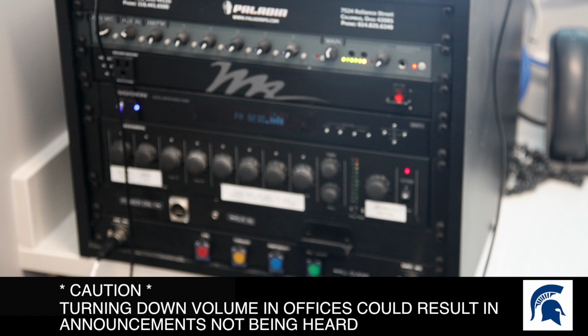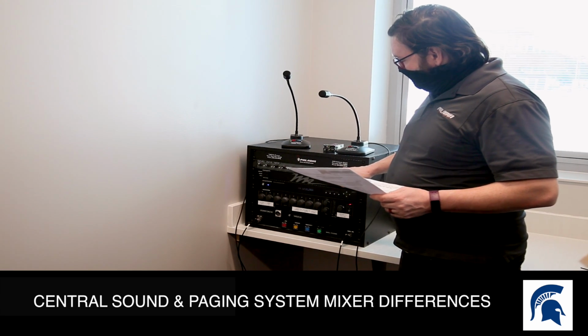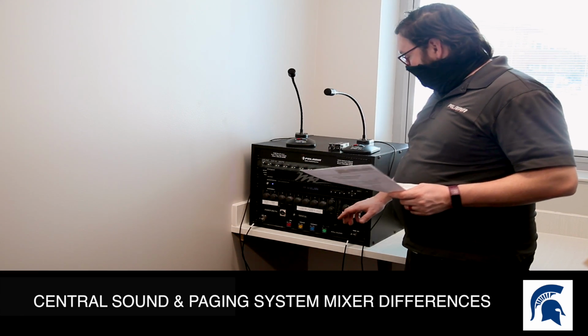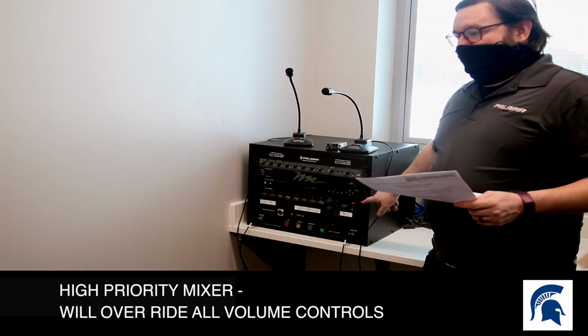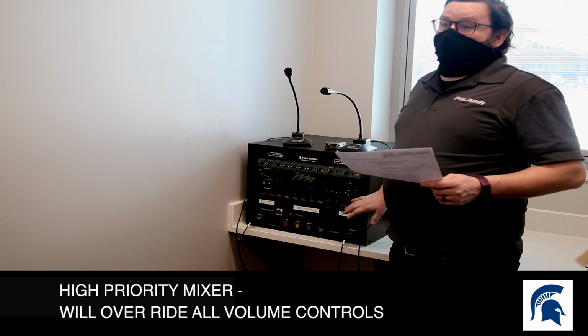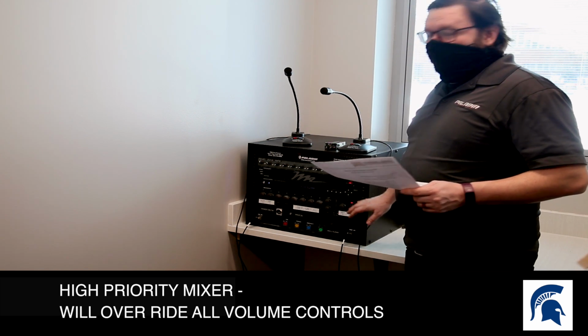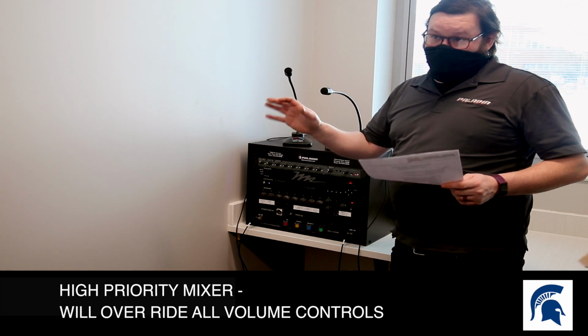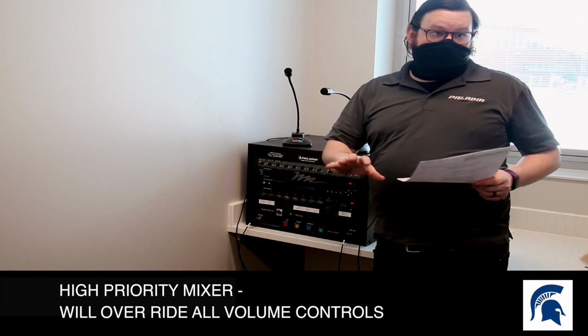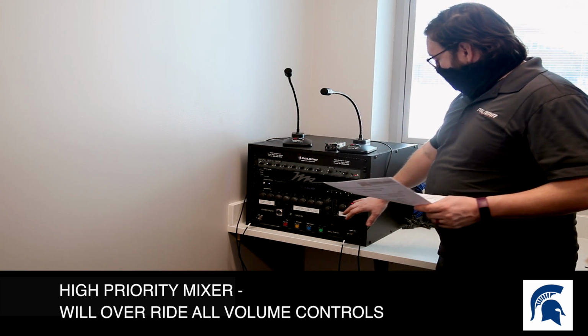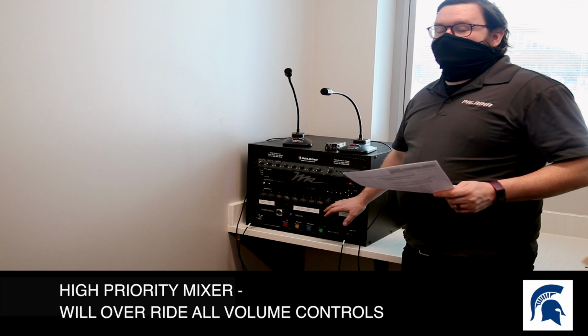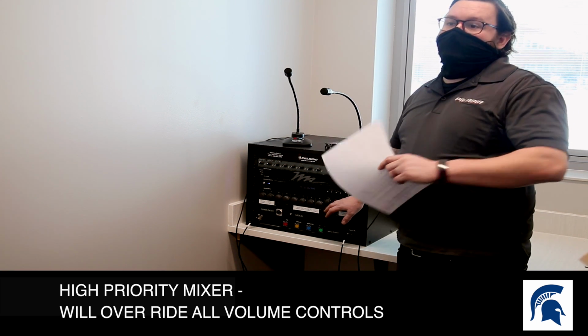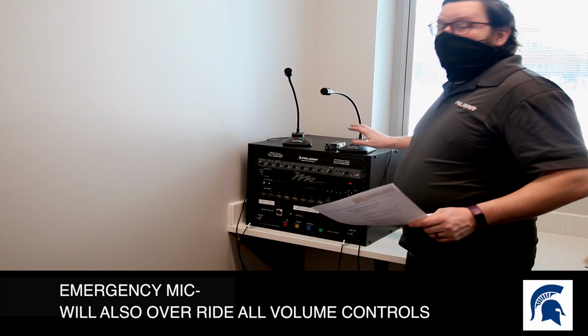When someone turns down their speaker, they won't hear general announcements from the phone system. They won't hear anything that comes through this mixer. The difference between this mixer and this mixer is that this is the high priority mixer. Anything that comes through this mixer will override those volume controls. So even if someone's got their speaker all the way turned down, if something comes through this mixer, the volume control will be bypassed. That includes the emergency mic.